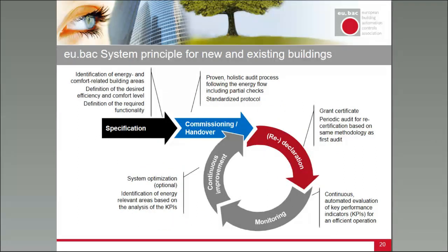Now, what we do with our methodology, the eu.bac system, is that you can enter into a project at the very early beginning, even in the specification phase, when the planner, the specialized engineers, are starting to develop the concept of energy distribution in the buildings. They can rely on this methodology and define the necessary functions and functionalities needed. Then during construction, or after construction in the commissioning and handover, the control engineers can audit the installed functionalities with this scheme and report the level of energy efficiency used.